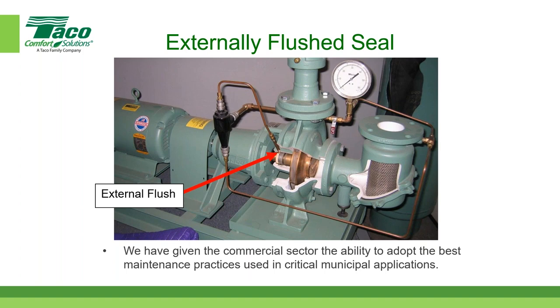They use water from the system and they spin it around in there, so they get the dirt and grit out, and they flush the seal. I think most pump manufacturers offer them. We offer them, and you can get more information from your manufacturer's rep. But those little brochures have some information about them as well. They're not very complicated. I'm not saying they're complicated, but what they do is very, very important, or possibly very important as well.